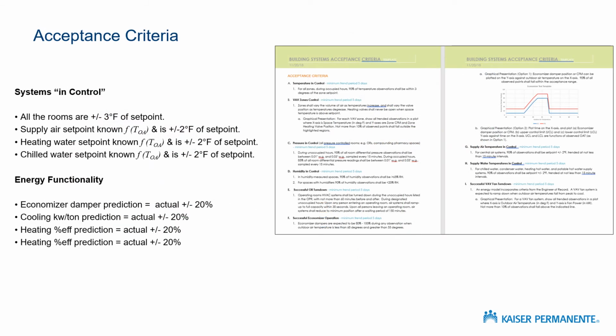So that leads us to acceptance criteria. What the hell is an acceptance criteria anyway? We have design firms say all the time, hey, that's not even in my scope of services. I was never hired to provide acceptance criteria. That's not in my contract, right? We actually hear that quite a bit. Well, here's the thing. When you're commissioning the system, there's going to be a trending period. It's going to last about 5 days. And the question is, how do we know from the data that we gather in those 5 days that the system is working perfectly, hopefully, according to your design intent?